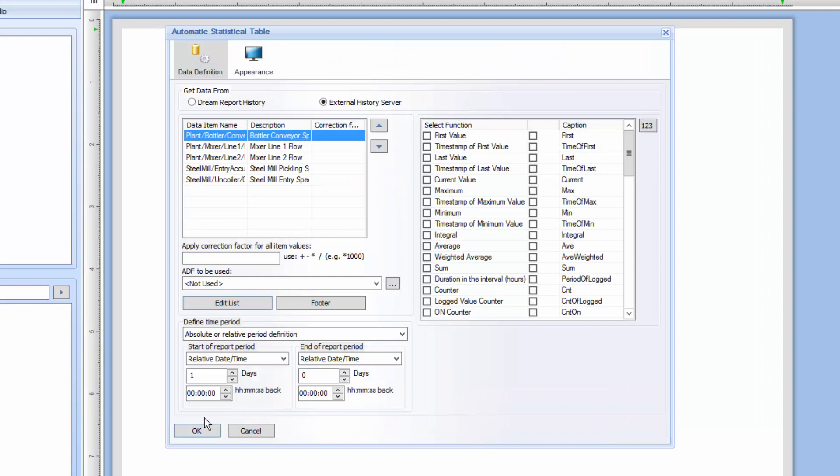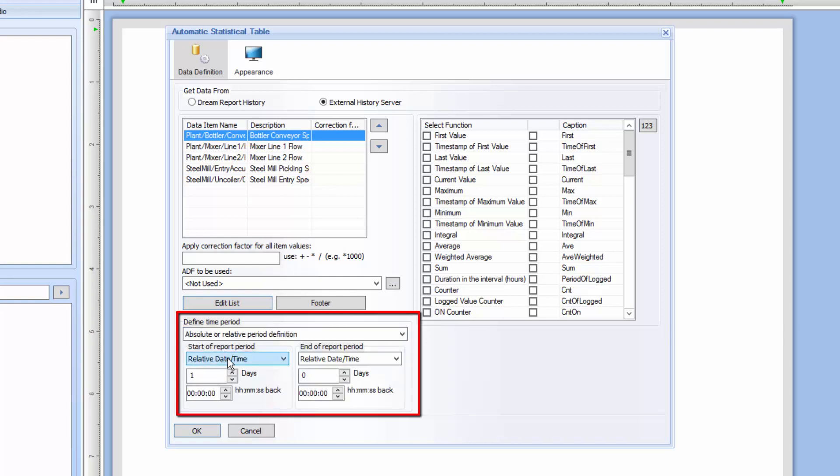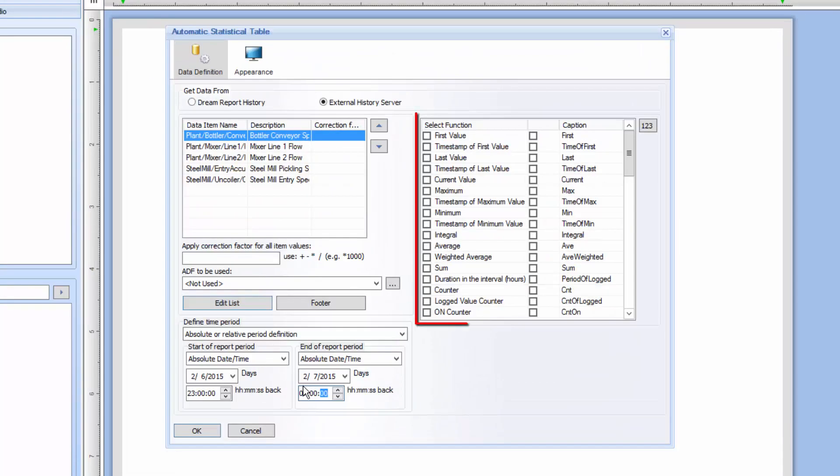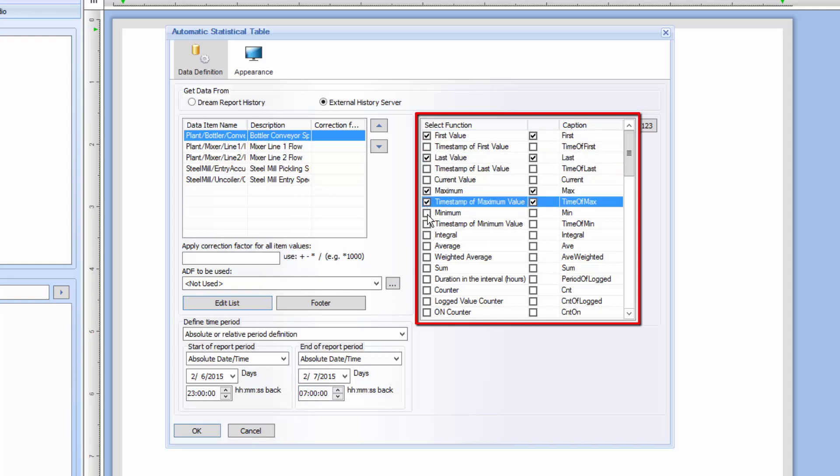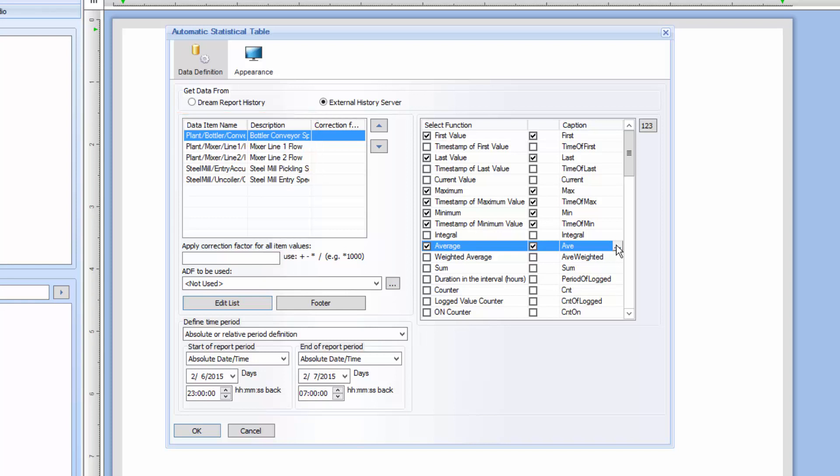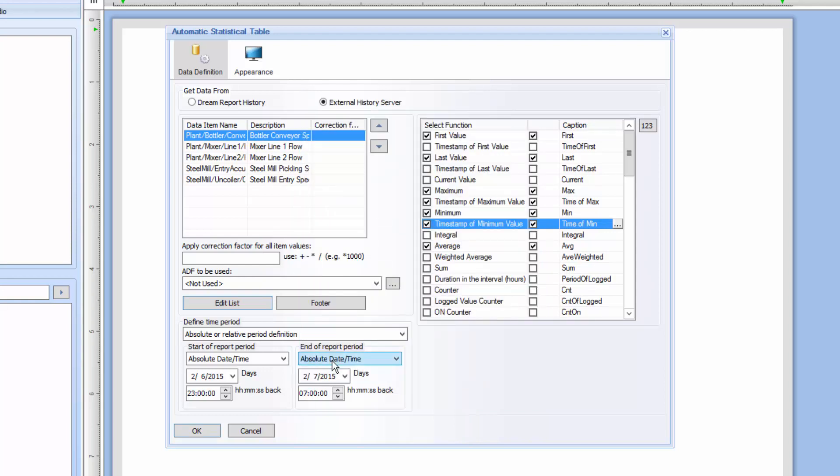Next, I'll select the time period to report on. Since this is a shift report, I typically use the last eight hours time definition. However, since my Citect historian is not currently logging data, I'm going to specify an absolute time period where I know I have third shift data in my historian. Finally, I'll select the various aggregates or statistical functions we want to include. Let's display the first and last values, as well as the min, max, and average values over that shift, as well as the times when the min and max values occurred. You'll notice that DreamReport exposes the tag descriptions as well from the Citect historian, which I could change if I wanted to for the purpose of this report. We can further configure each of these functions if necessary for conditional formatting, decimal places, captions, engineering units to display, etc. Detailed configuration of the automatic statistic table is covered in a dedicated video tutorial.